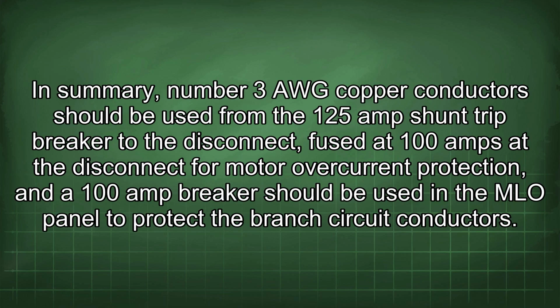In summary, number 3 AWG copper conductors should be used from the 125 amp shunt trip breaker to the disconnect, fused at 100 amps at the disconnect for motor overcurrent protection, and a 100 amp breaker should be used in the MLO panel to protect the branch circuit conductors.